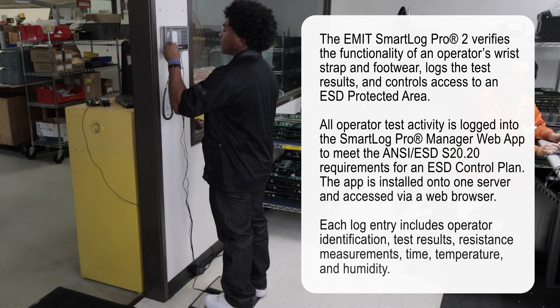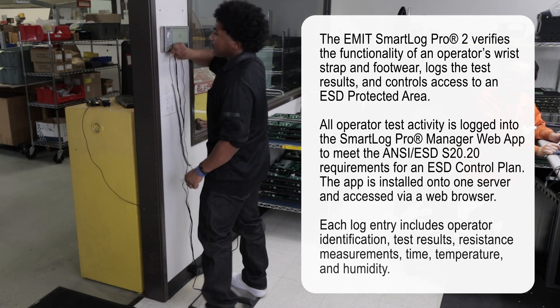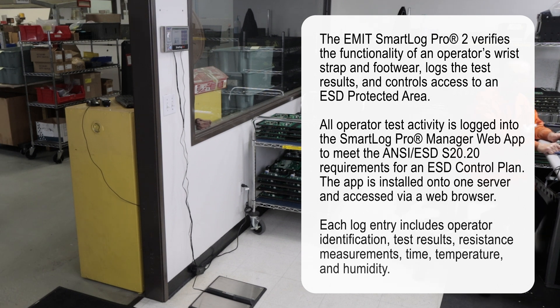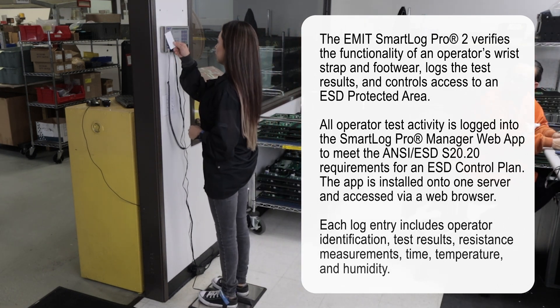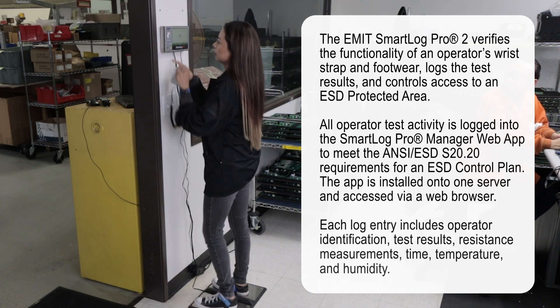The EMIT SmartLog Pro 2 verifies the functionality of an operator's wrist strap and footwear, logs the test results, and controls access to an ESD-protected area. All operator test activity is logged into the SmartLog Pro Manager web app to meet the ANSI ESD S20.20 requirement for an ESD control plan.